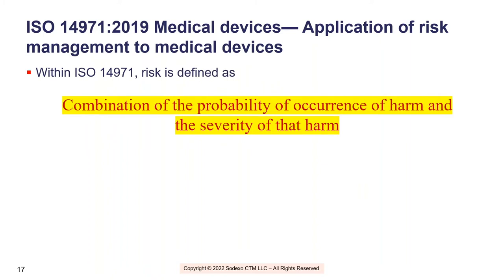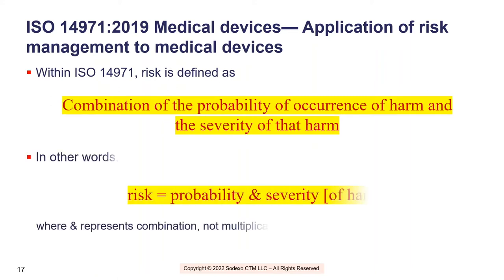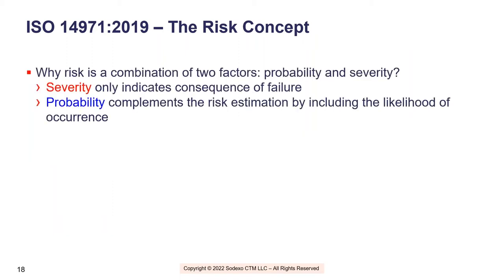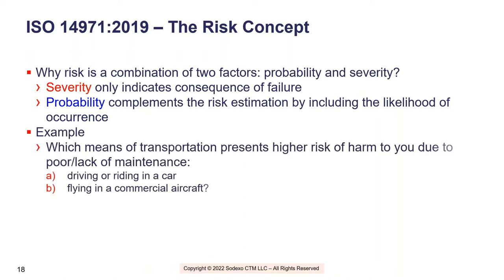ISO 14971, 2019—we identify the combination of probability of occurrence of harm and the severity of harm. In other words, probability and severity equals risk. Some of you are familiar with the Joint Commission model, where you have nine blocks of probability and severity—it's the same model, or very similar. So why is it the combination of two factors? Severity only indicates the consequences of failure, while probability only looks at the likelihood of the occurrence.